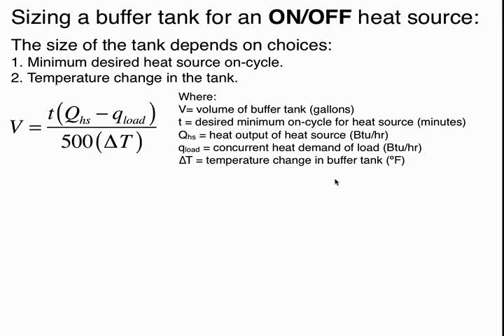We need to know what is the output of the heat source. Now, this is, again, for an on-off heat source. So if we know the rated heat output of the heat source, that would be this QHS here. Q load would be any load that we know is on when the heat source is on.